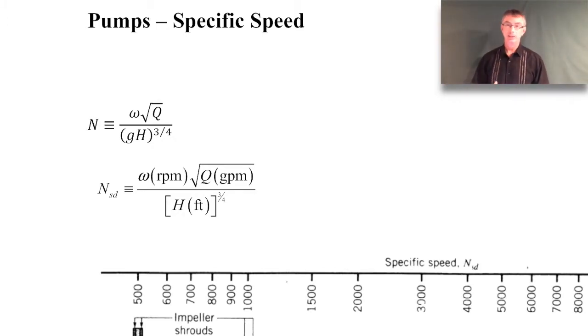So again, in your particular application, presumably you would know what your requirements are for flow rate and head rise. Because the rotational speed is often dictated just by the motor that drives the pump. A lot of motors have predefined speeds, like AC motors might operate at close to 1800 RPM or maybe 3600 RPM. That's just the way that many motors are designed. And so omega would also be something that you presumably would know.